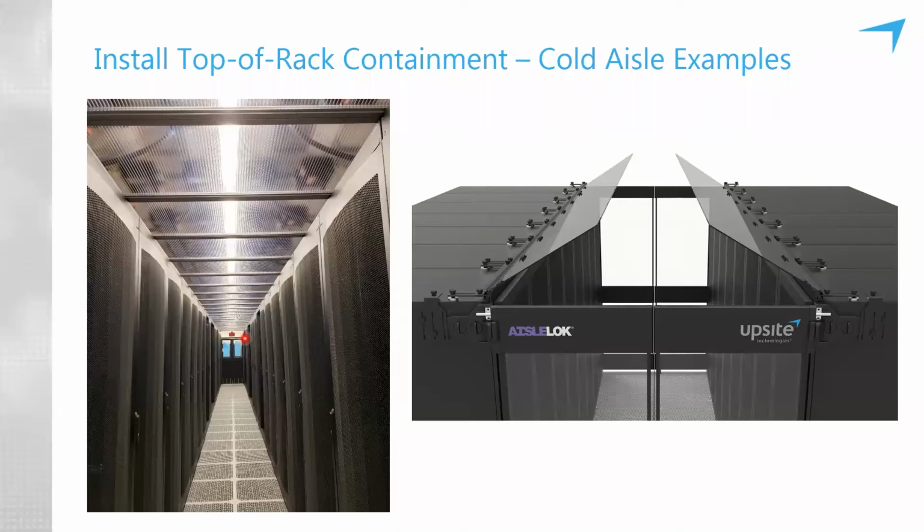But nonetheless, the capped aisle, these are panels. Think of a picture frame. So you've got an aluminum frame with an insert there with some special material that shrinks. It doesn't melt. It deforms and falls out of the frame when it reaches about 135 degrees. And that's before the temperature of a sprinkler head might go off above it.